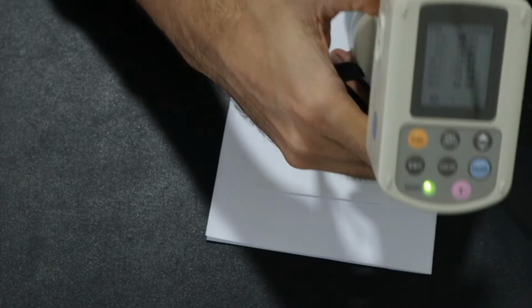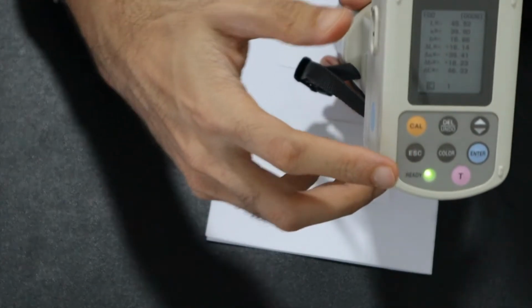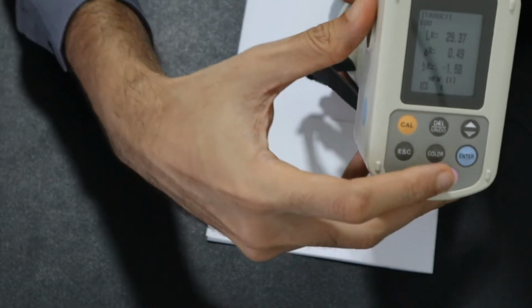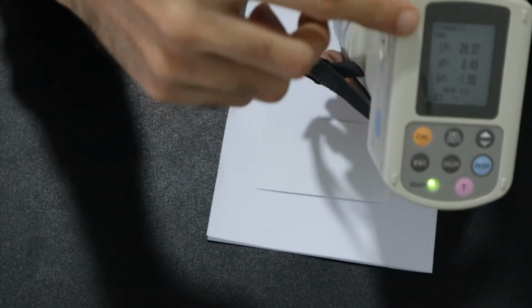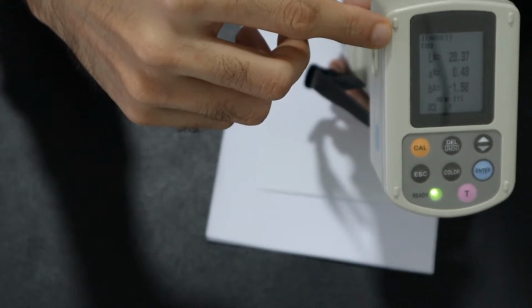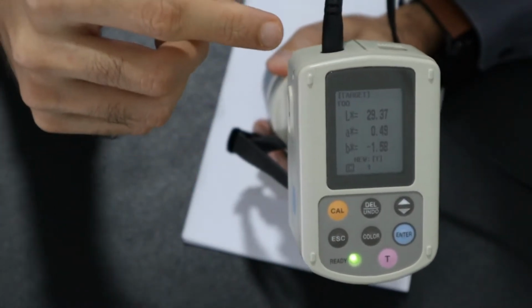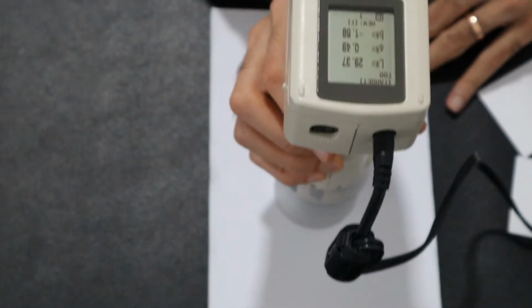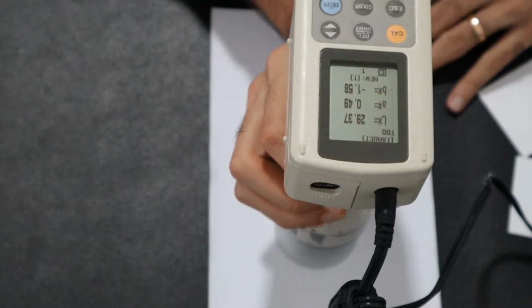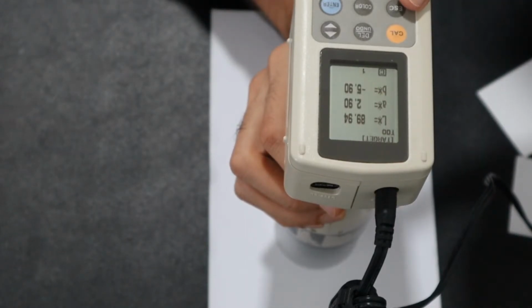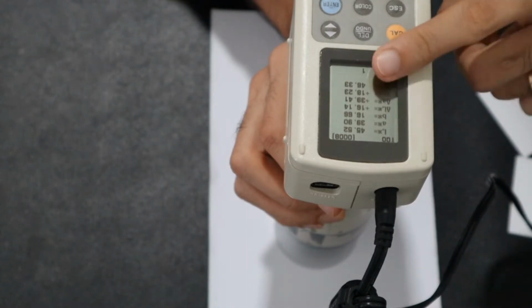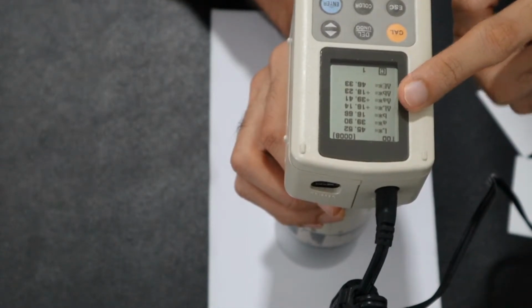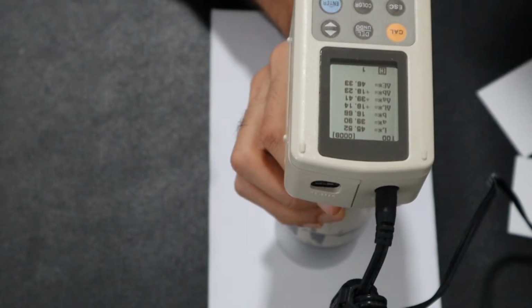To do color difference measurement, it's rather simple. On the equipment, I press the button which says T. T stands for target, and here you see there's T00 and some value, which means that target 00 has already been assigned a value. If you would like to override this value, it's very simple. I just measure on T00. This sets a new target value for T00, and the screen immediately changed back to the default screen, which means that the target has been captured and is ready for sample measurement.